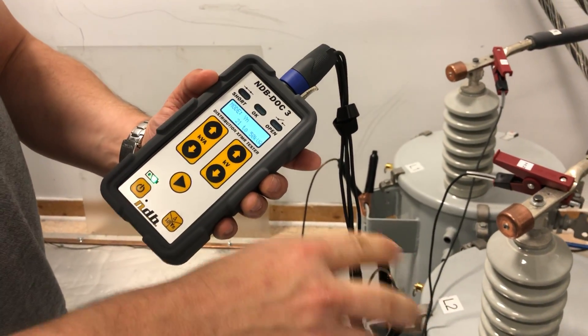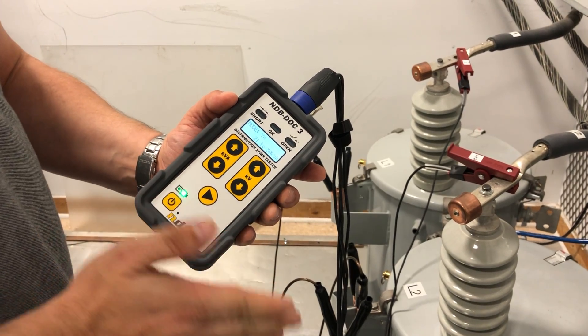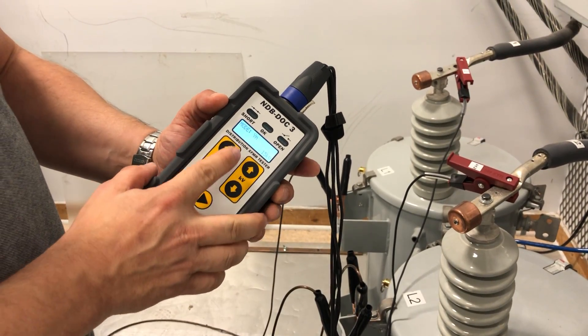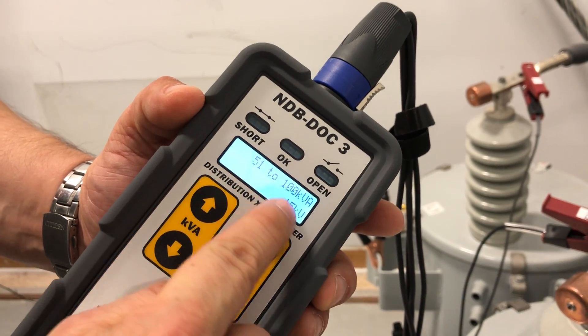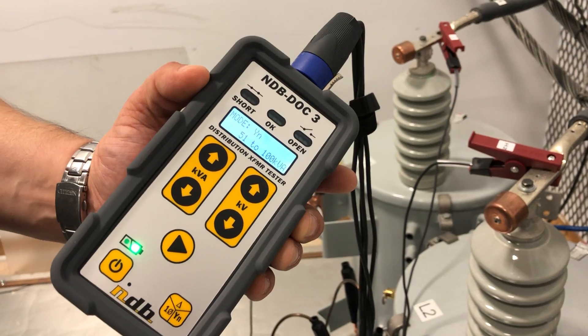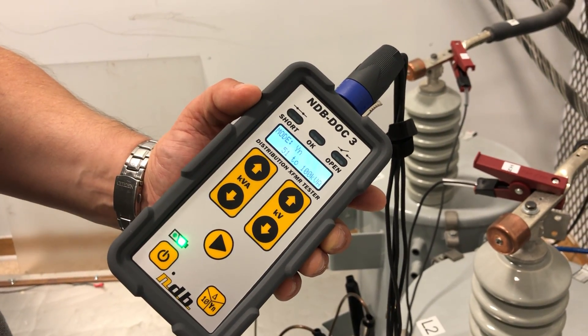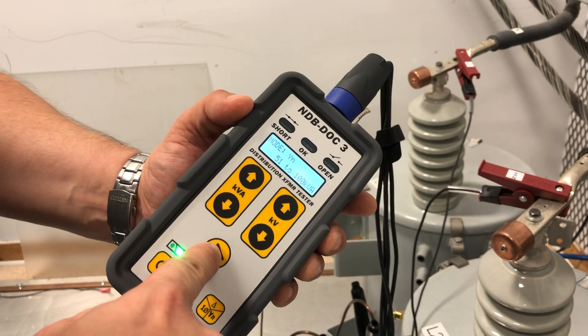These transformers are all single-phase 25 kVA, so we need to add all three to give us 75 kVA. So I'm going to have to select the range between 50 and 100 kVA. The voltage selection has to be — since it's a Y — phase to neutral, and that is 15 kV. That's what we have.